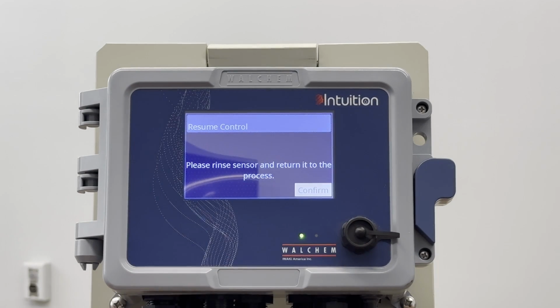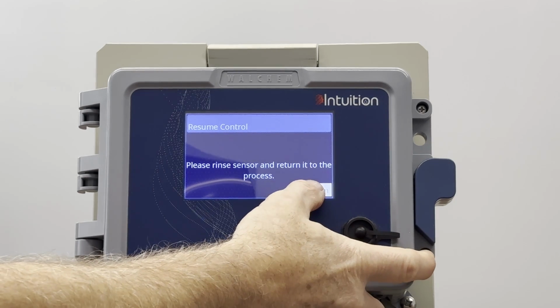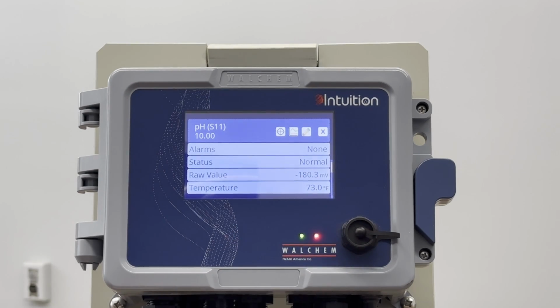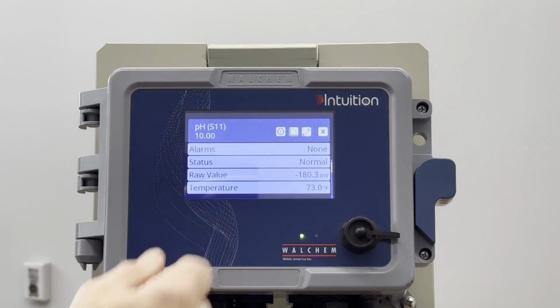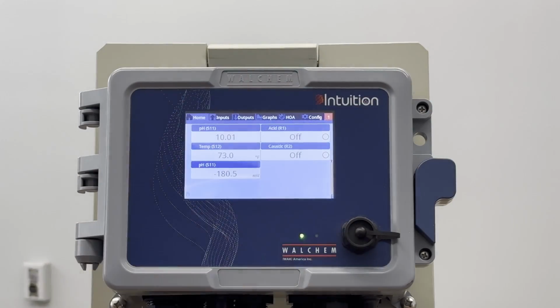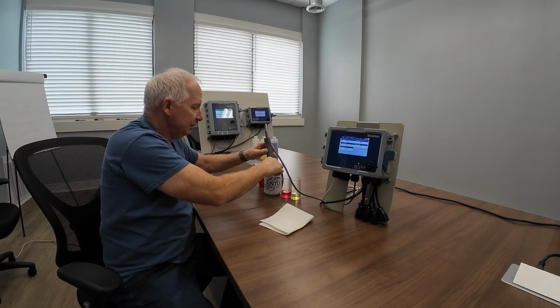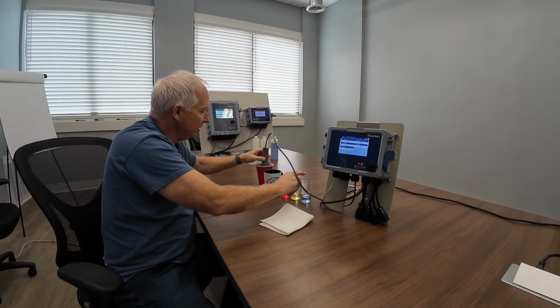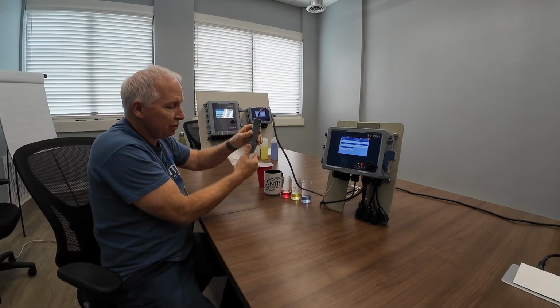It says, do you want to rinse the sensors and return it into the process? And I say, yeah. Now, at that time, it would start using the relays again, which is why at the very beginning I turned them off. And I'm just trying to make sure that we're not feeding a bunch of acid now, that it's sitting here in a buffer of 10. And the reason I do this is I want to see what readings I'm getting just to verify that the calibration was working. So I'm sitting here at 10. I've got a millivolt value of minus 180.3, minus 180.4. So obviously it reads 10 very well. And I'm just doing this to verify that the whole calibration process was accurate.